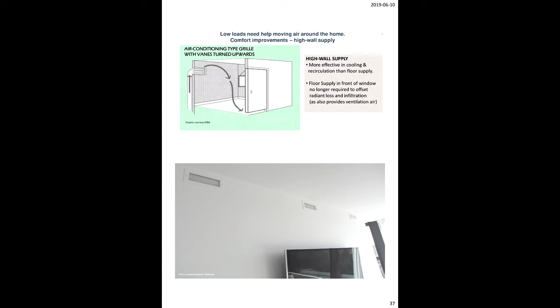Let's get rid of some ductwork. Let's put in high wall. Let's move the air a little faster, not high velocity, mid velocity. Let's get it out of the occupied zone, 6 inches from the ceiling, and let's start to mix the air in the room quietly but effectively. So again, right now there are some issues with the ability to do this. You either need a PEng to sign off for you or they won't accept it, but the HRAI design guidelines for air system design is currently being redone, and it's going to change this so that designers for residential can actually do up to 1 static or higher, which will make this happen.